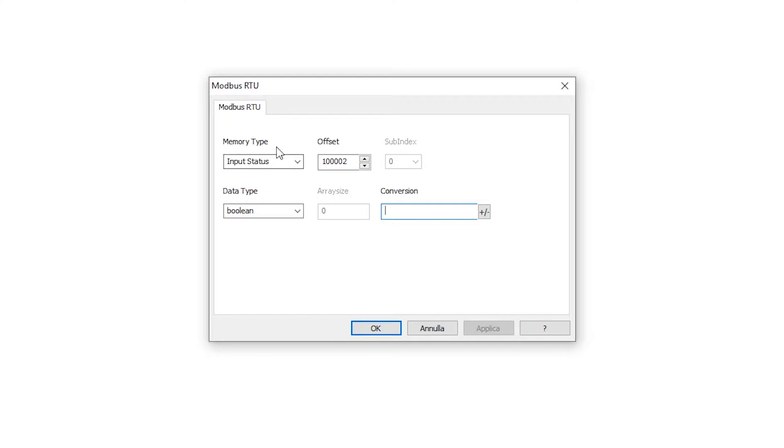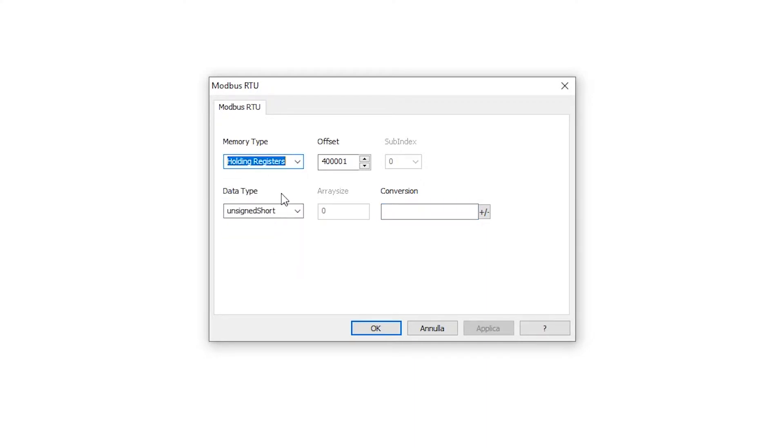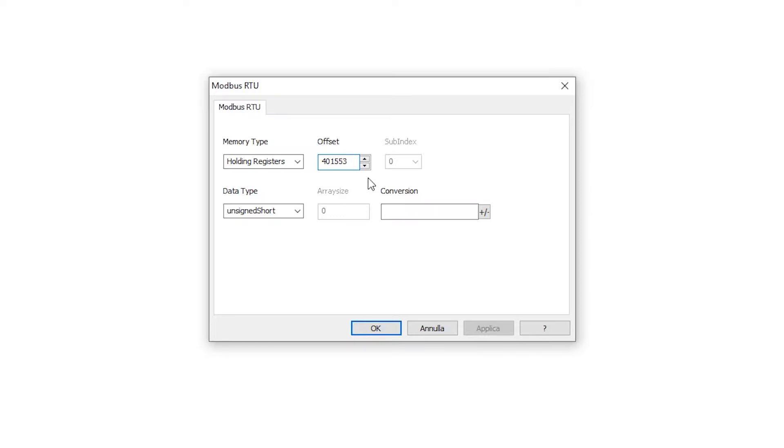In the Memory Type field, select Holding Registers. And in the Offset field, enter the address of the tag in decimal. In our example, 1553, added to the value 400000, convention used by the Modbus protocol for registers.